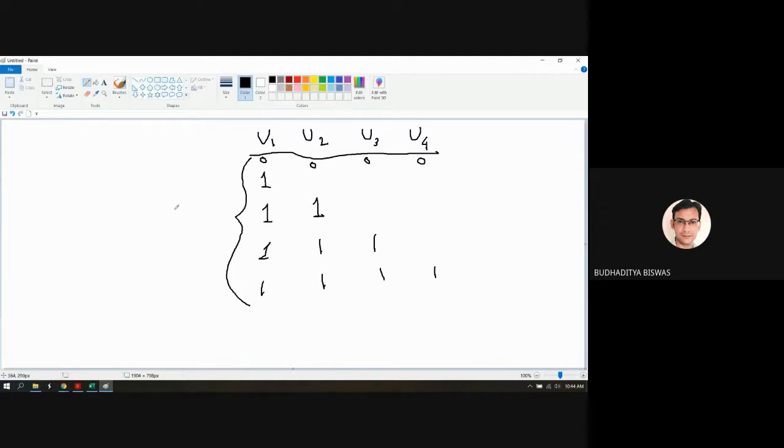And among the 5 combinations, we must choose the best one to meet the load demand. And this one is called the dynamic programming sequential combination. And as you see, this one is quite similar to the priority list method. But here both the units should be switched on at a time if load demand is not successfully met by the unit 1. So that's why this will also not give the most economical solution. This is called the suboptimal solution. And this is called the DPSC. We use the DPSC when there is a huge load demand change.